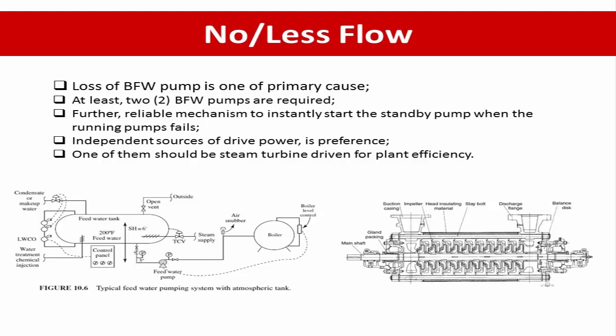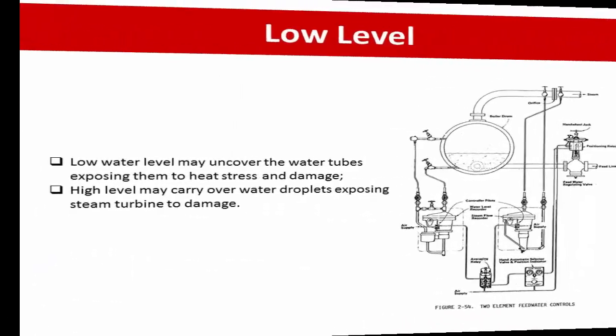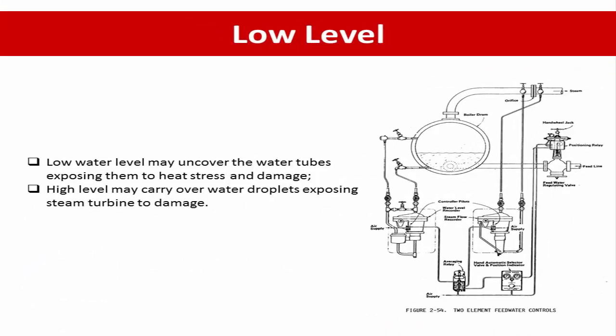Another cause of no or less flow to the boiler during HAZOP review is malfunction of flow control, where the flow of feed water to the boiler drum is normally controlled in order to hold the water level in the steam drum as close as possible to the normal water level. Low water level may uncover the water tubes, exposing them to heat stress and damage, while high level may carry over water droplets, exposing the steam turbine to damage.